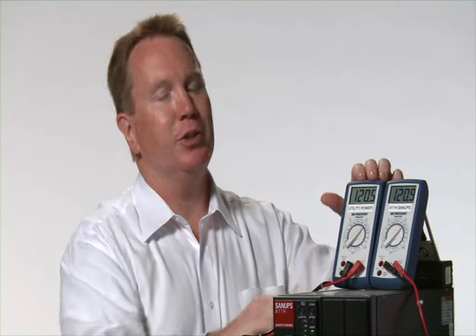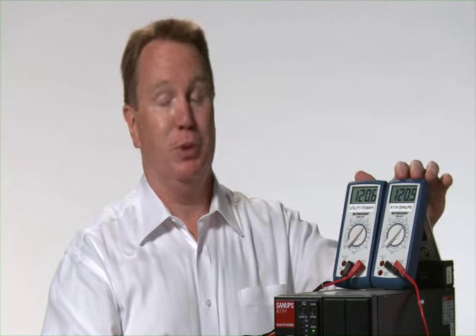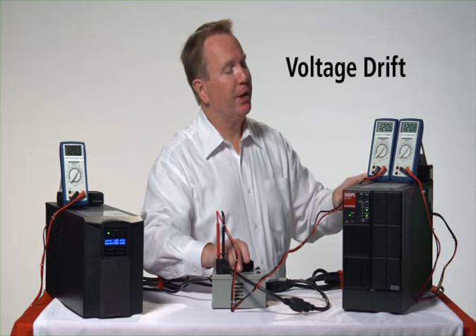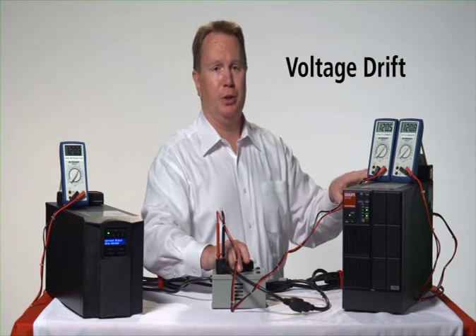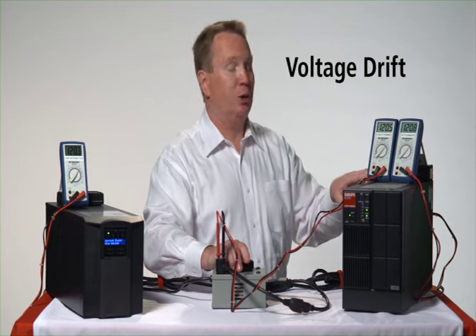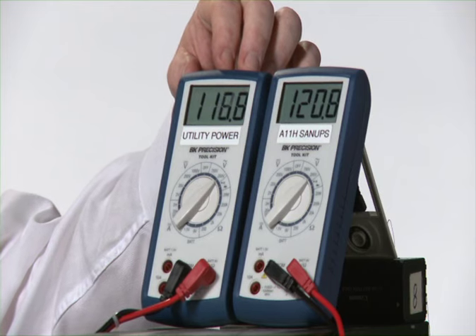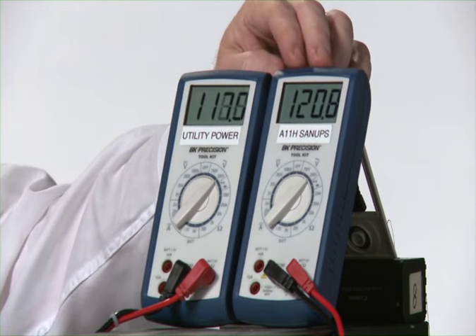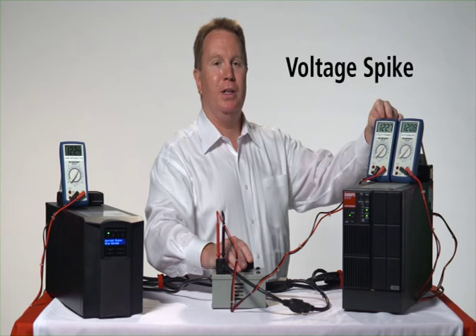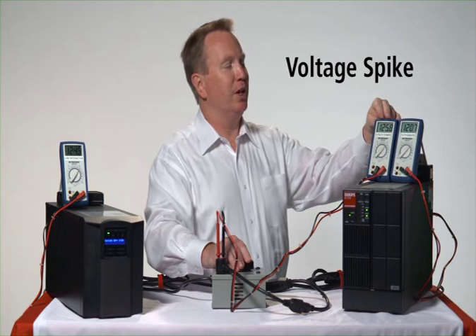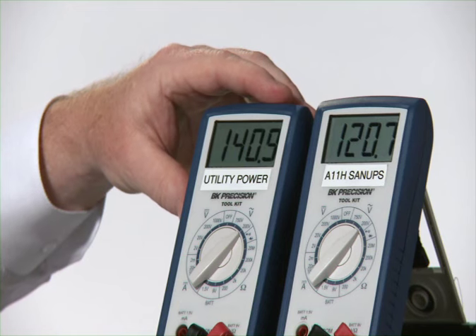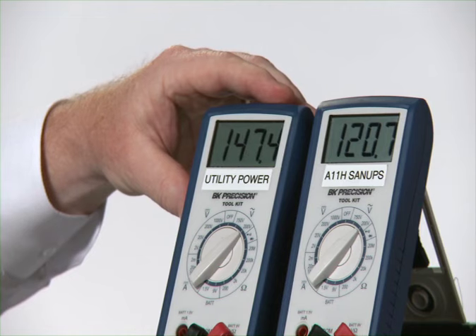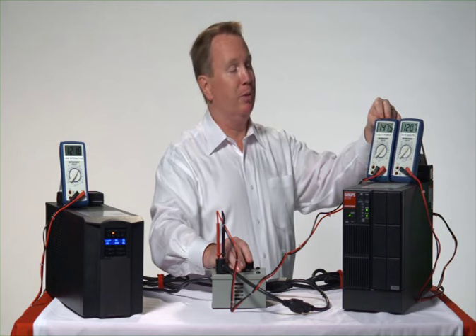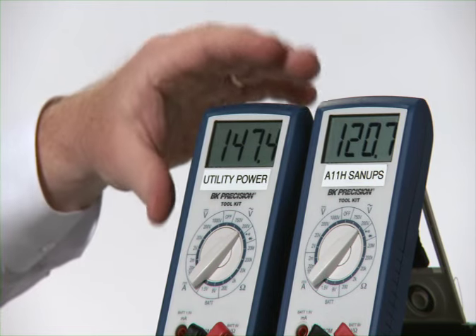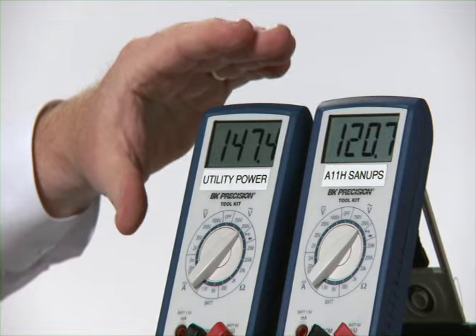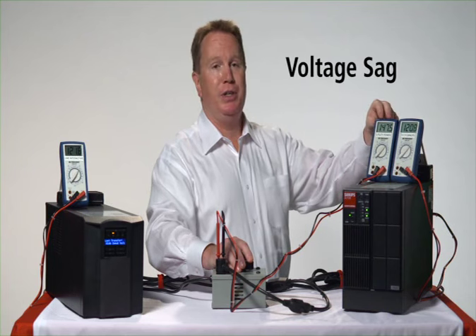Once again, this is your utility input voltage, and this is the precision voltage that your equipment is seeing. One of the primary characteristics of the true online double conversion is that as input voltage changes, output voltage doesn't, as demonstrated in the drift. No change in output voltage. Let's continue to the spike. Now our voltage climbs back to the 140 level, past the 140 level. Now, our line interactive unit is in a full battery mode, but our true online double conversion, there's been no change in the output voltage, maybe 1/10 of a volt, and we are still online. Let's proceed to the sag.